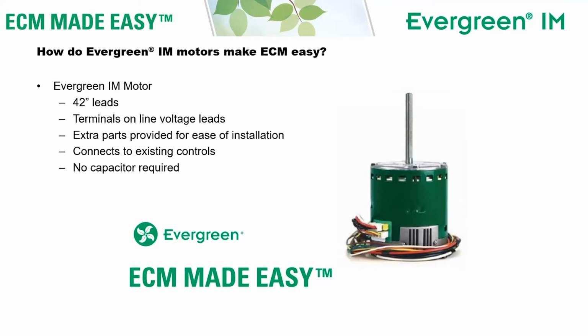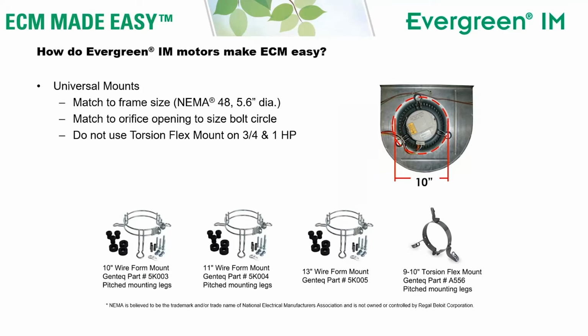There are terminals on the line voltage leads, extra parts provided for ease of installation, and this motor will connect directly to the existing controls in the HVAC system. You will not need any extra controls or wires. And it also eliminates the capacitor used with the traditional PSC motor. The motor is a 48 frame motor, which is approximately 5.5 inches in diameter, and it will fit any 48 frame belly band mount. So if the motor you're taking out is sliding out of a belly band mount, you'll be able to slide the Evergreen motor back into that same mount.